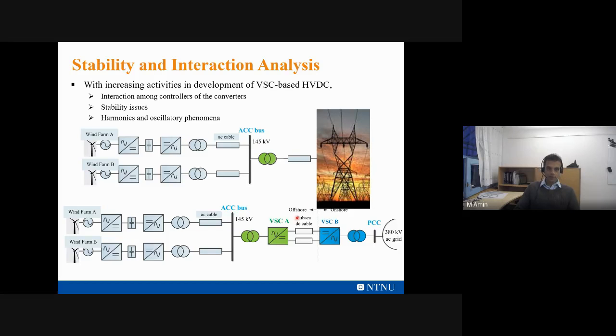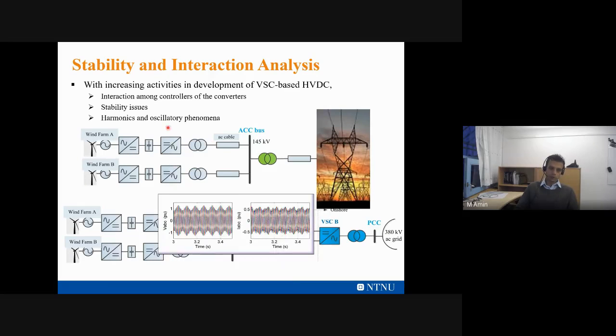As a result, this introduces instability problems, harmonics, and subsynchronous oscillation problems in the grid, like this one. Even when we design each wind turbine assuming it's connected to a strong grid, it works fine at the design stage. But when we connect many of them together in a layout, we can see subsynchronous oscillation or harmonic problems appear in the system.